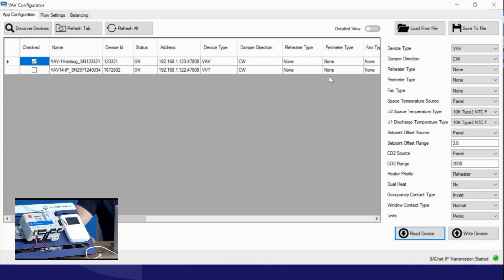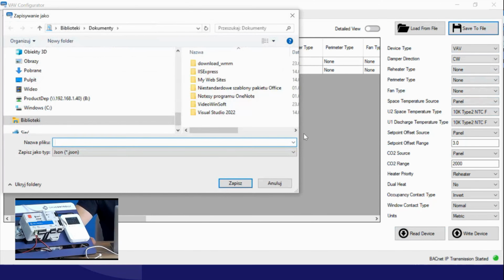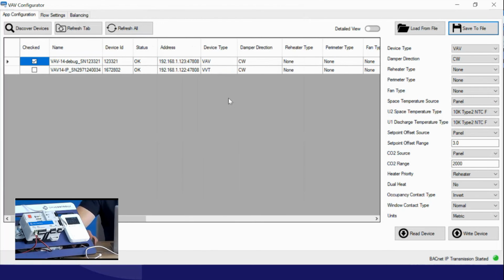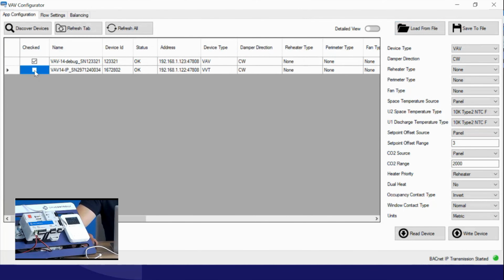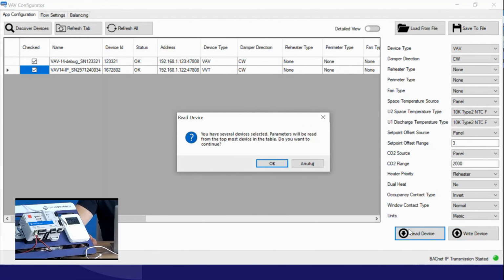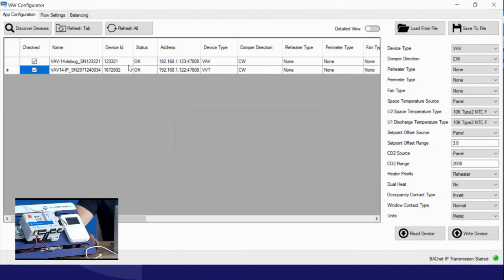So I will read all the parameters and I can save this configuration to a file. To deploy the same configuration to the next controller on the bus, I can do the same using load from file. I can read it, select the controllers, and write the configuration to the selected controllers. A pop-up window just appeared, informing me about the status of the deploying. Just hold for a while, like always on a live demo. I need to refresh the tab to see that the configuration has been changed.